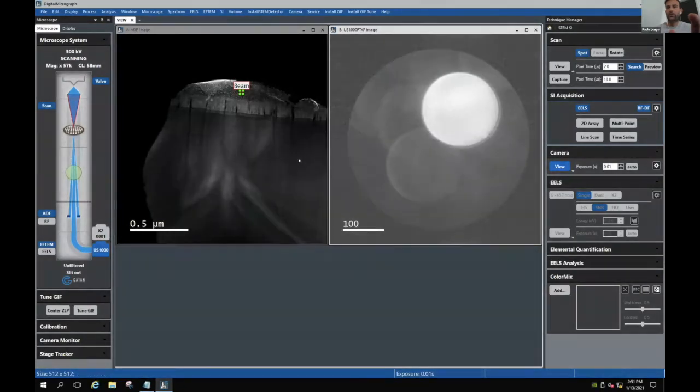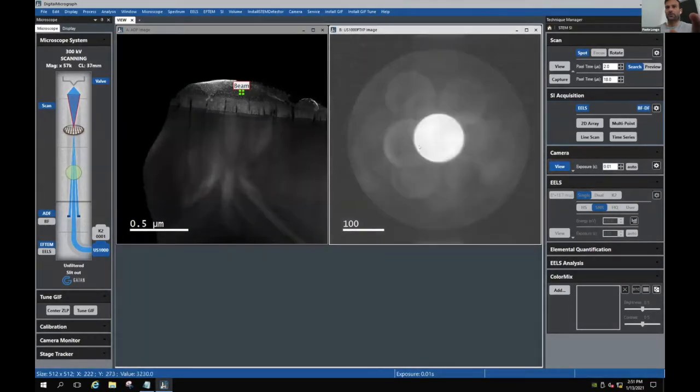One of the reasons for the importance of the GIF is that you can make sure the beam is always crossing the center of the aperture. Ideally, with the diffraction alignment, you can move the beam to the center. So Robert is going back to 37 millimeters. Now you see that the beam is going right at the center of the spectrometer entrance aperture.